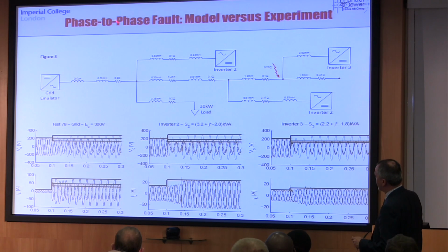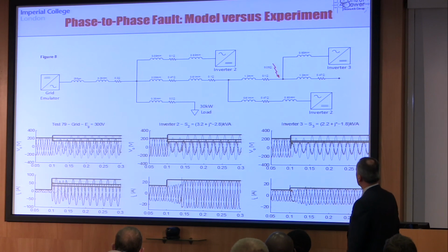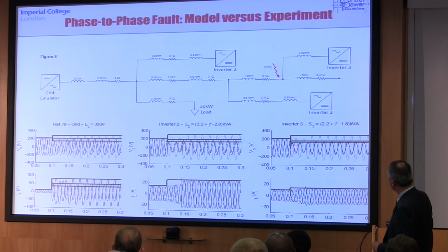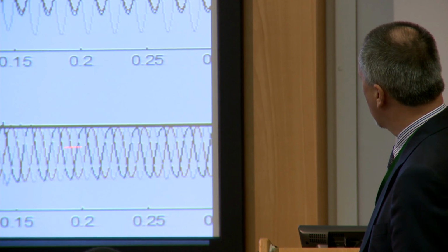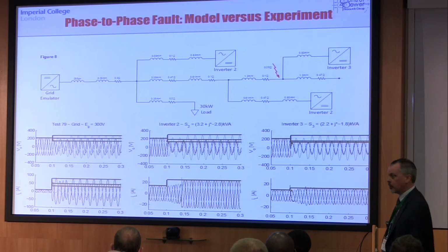This was a phase-to-phase fault, so an asymmetric fault. And you see that in the time domain waveforms here close to the fault. Two phase voltages are pulled together and the third phase voltage pushes up, and you get a series of fault currents. The solid lines are what is predicted by the equivalent impedance model, and that agrees quite well with the time domain models.